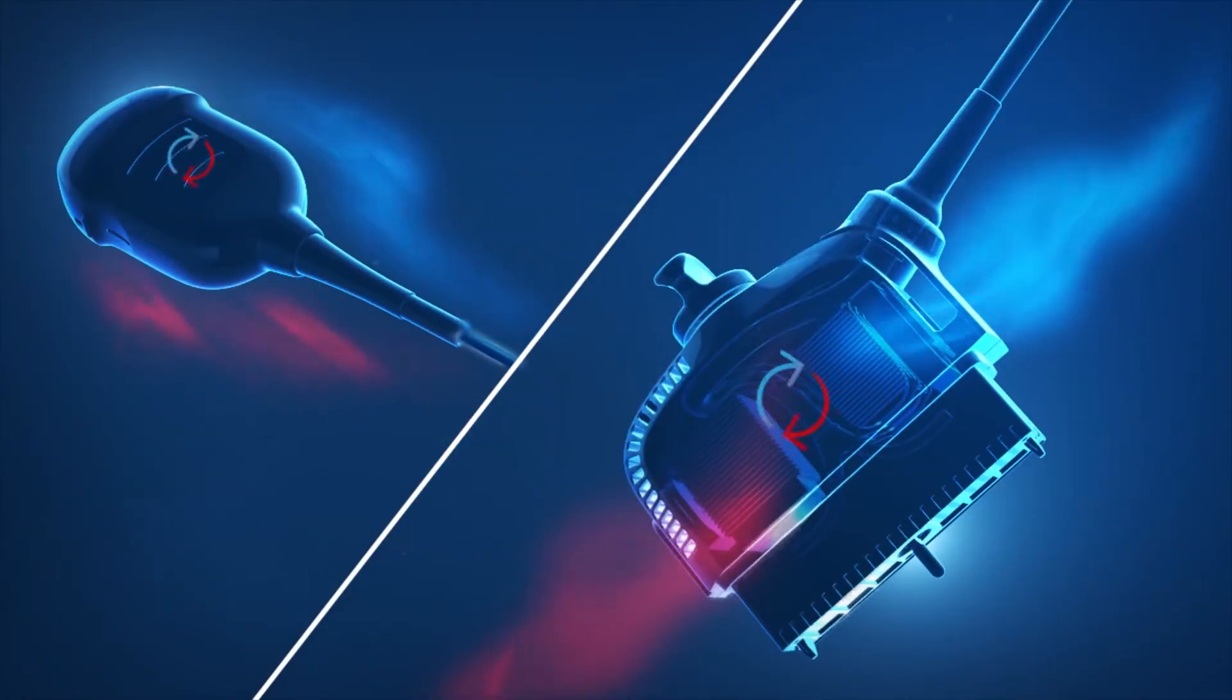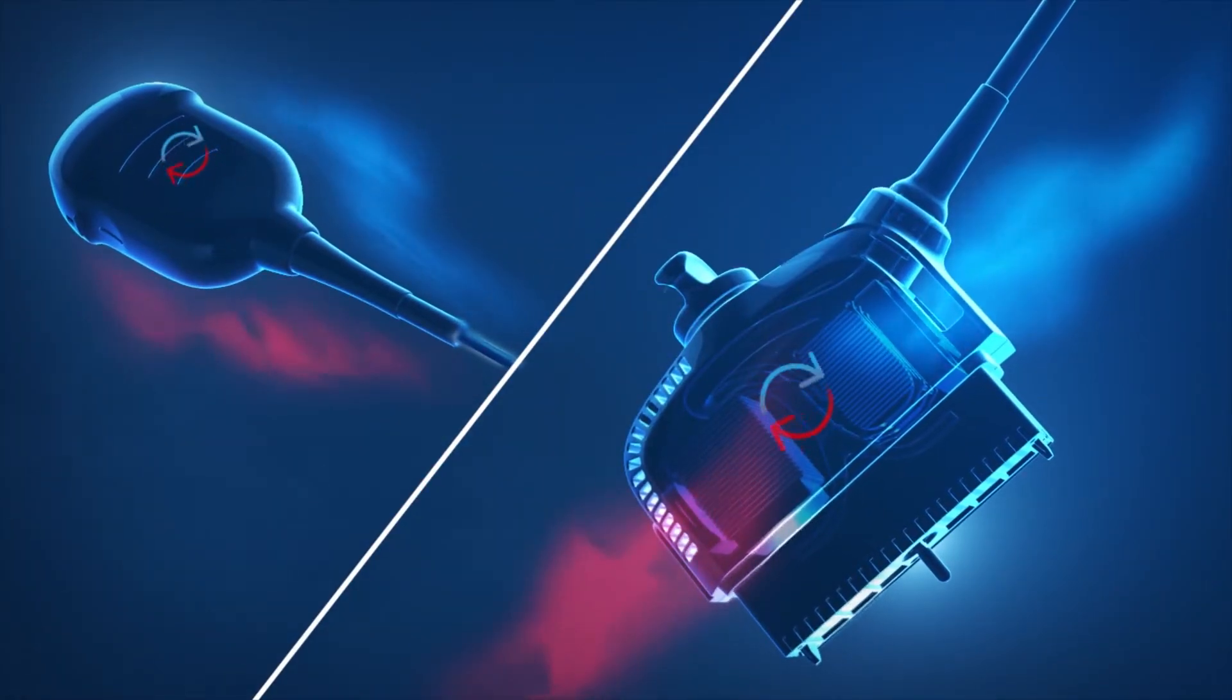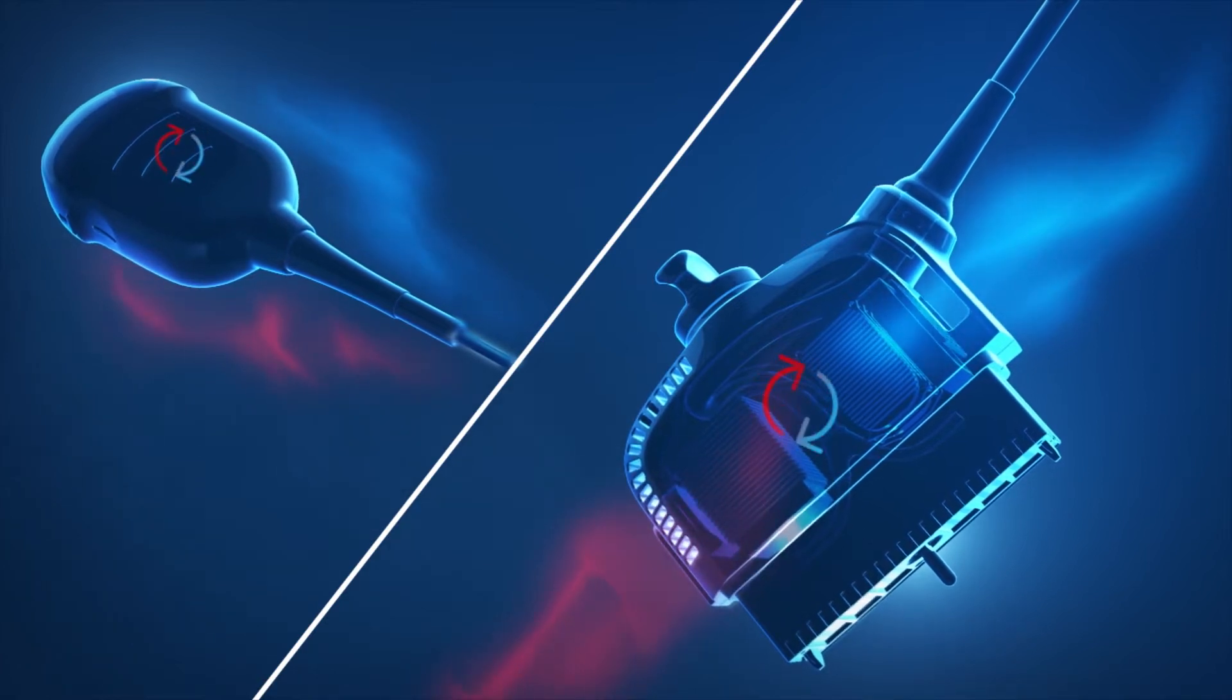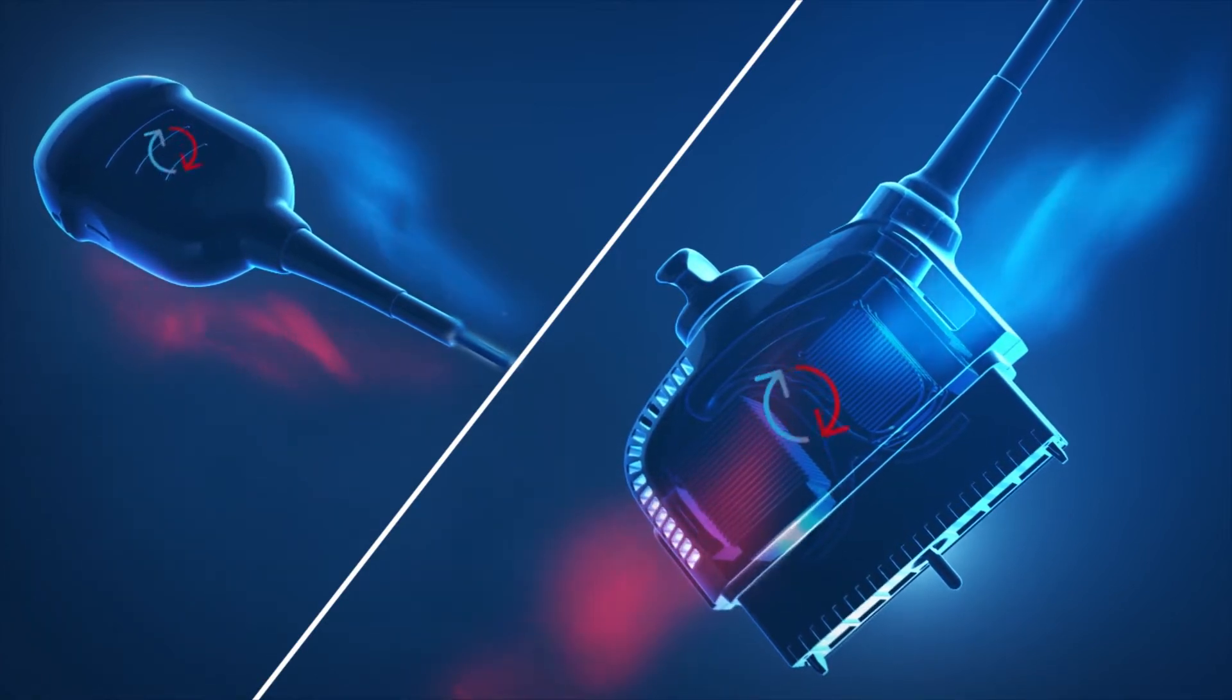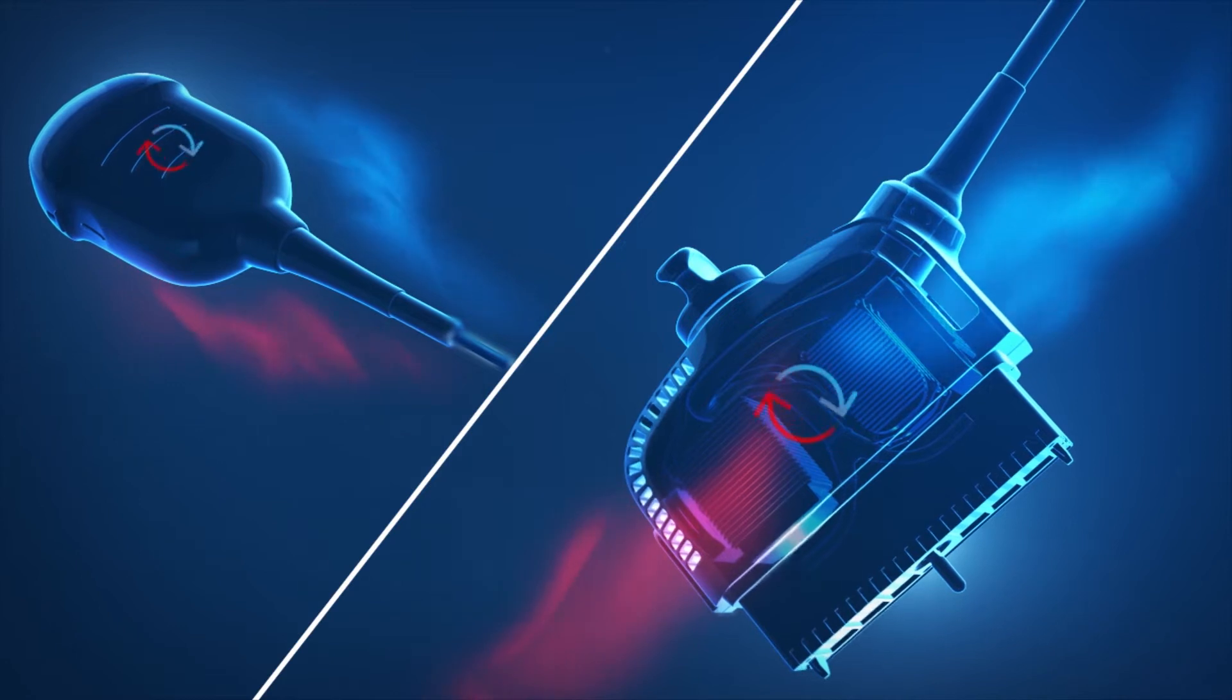To dissipate heat, the EM6E probe uses active cooling, allowing the EM6E to achieve greater penetration, frame rates, and image quality when compared to probes using passive cooling techniques.